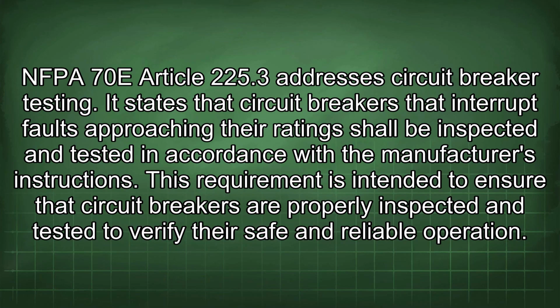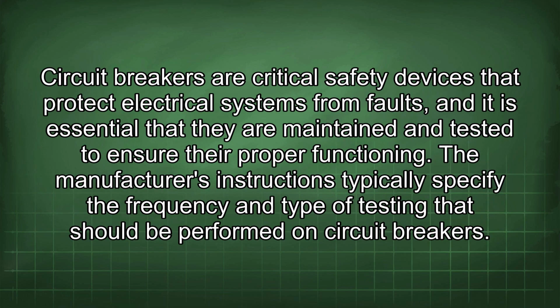NFPA 70E Article 225.3 addresses circuit breaker testing. It states that circuit breakers that interrupt faults approaching their ratings shall be inspected and tested in accordance with the manufacturer's instructions. This requirement is intended to ensure that circuit breakers are properly inspected and tested to verify their safe and reliable operation. Circuit breakers are critical safety devices that protect electrical systems from faults, and it is essential that they are maintained and tested to ensure their proper functioning.